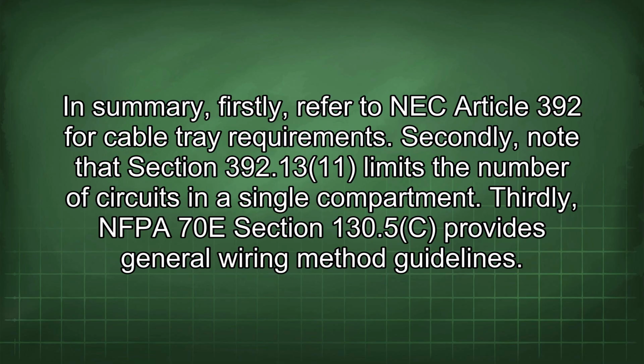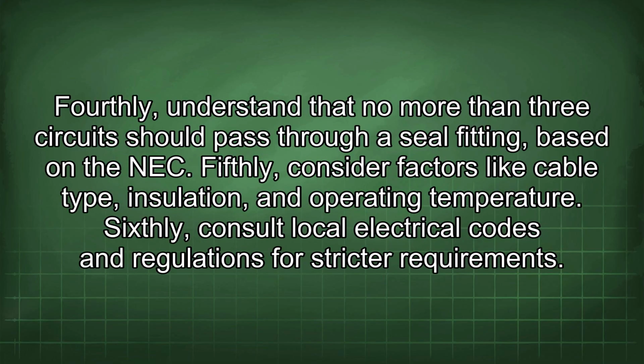In summary, firstly, refer to NEC Article 392 for cable tray requirements. Secondly, note that Section 392.13(11) limits the number of circuits in a single compartment. Thirdly, NFPA 70E Section 130.5(C) provides general wiring method guidelines. Fourthly, understand that no more than 3 circuits should pass through a seal fitting based on the NEC. Fifthly, consider factors like cable type, insulation, and operating temperature. Sixthly, consult local electrical codes and regulations for stricter requirements.